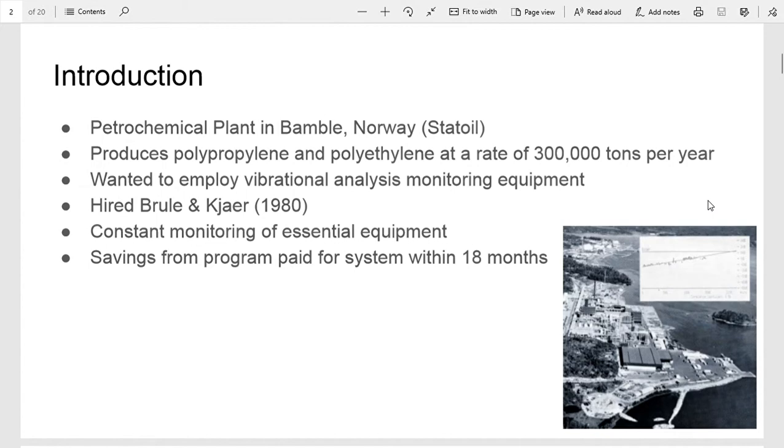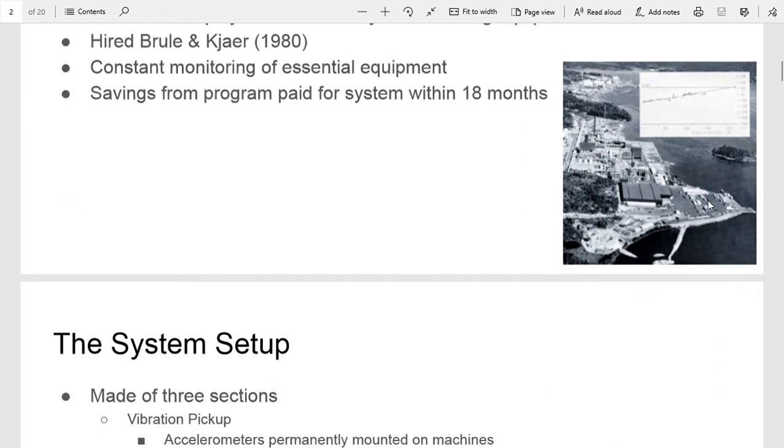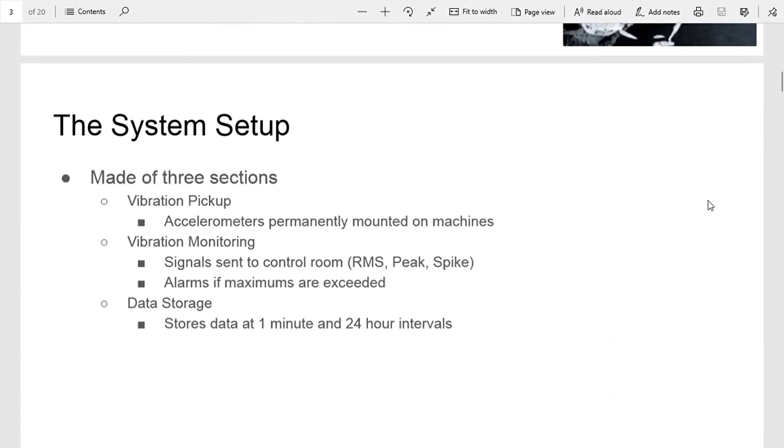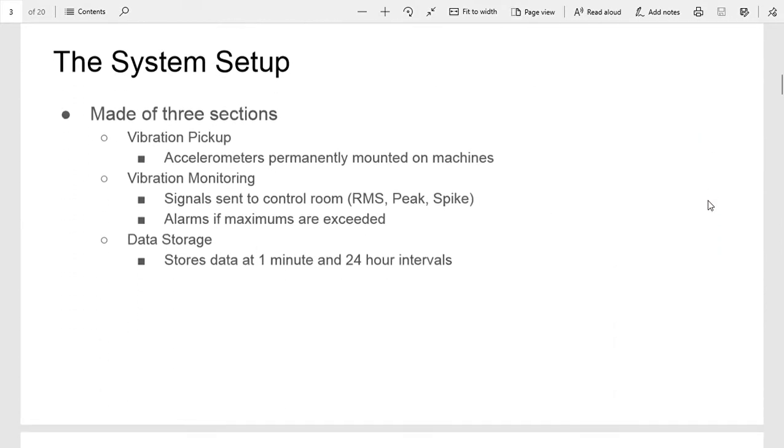They wanted to install a constant monitoring system for their essential equipment, and the savings from the program that they installed actually paid for the system within 18 months. So pretty good cost return. The basic setup had three sections total, where the vibration pickup, which was accelerometers permanently mounted on machines in various places, had those signals fed into a main control room.